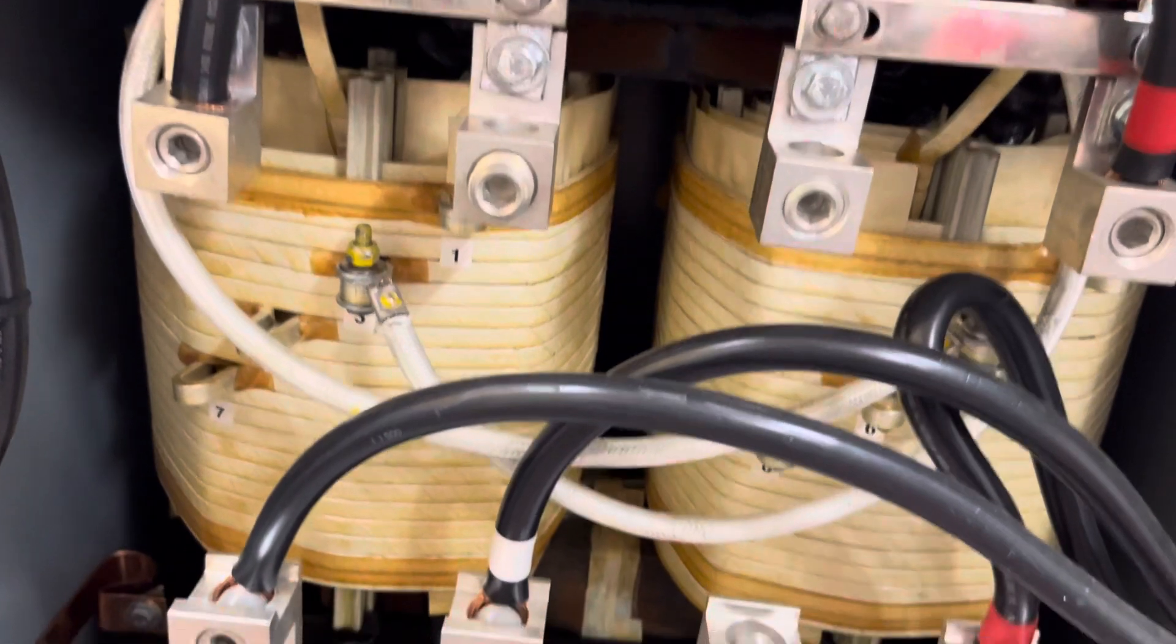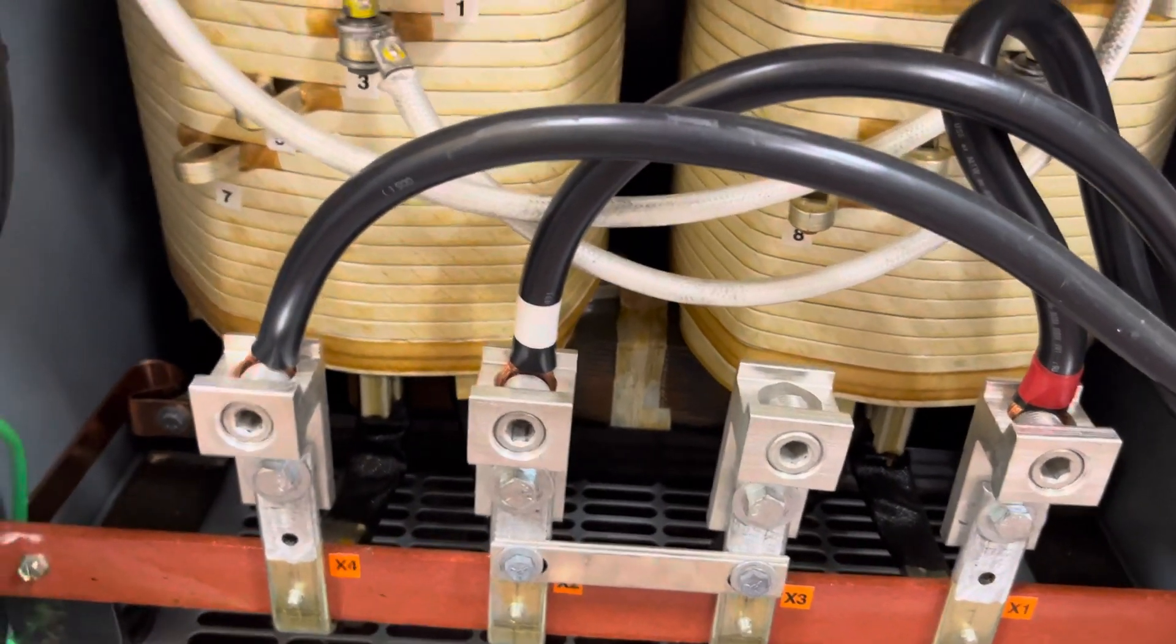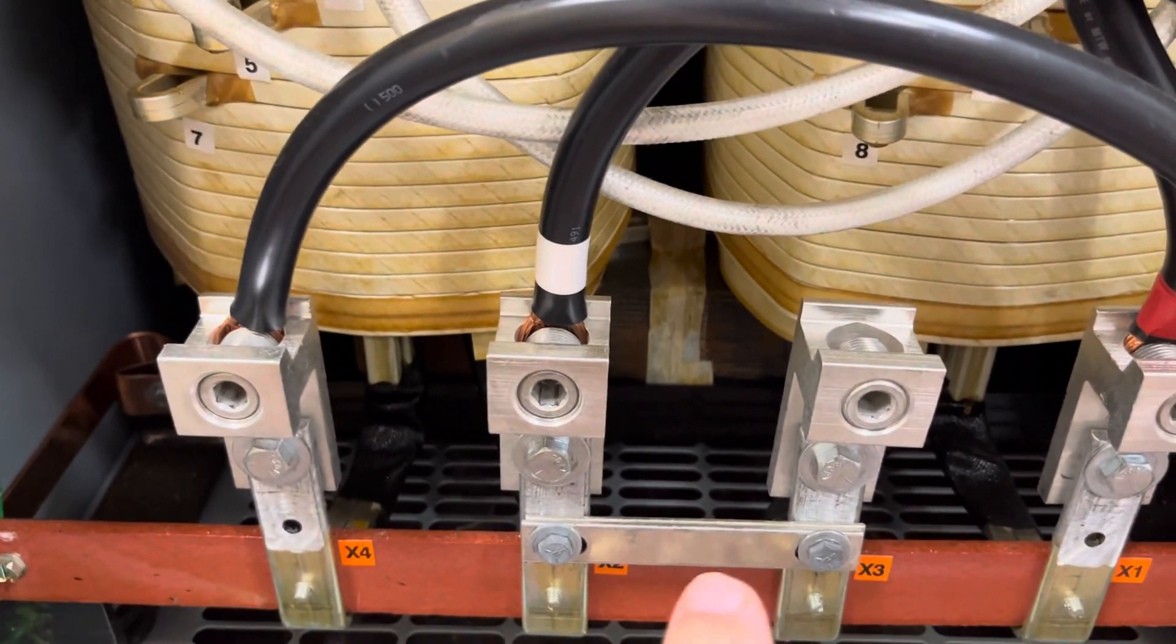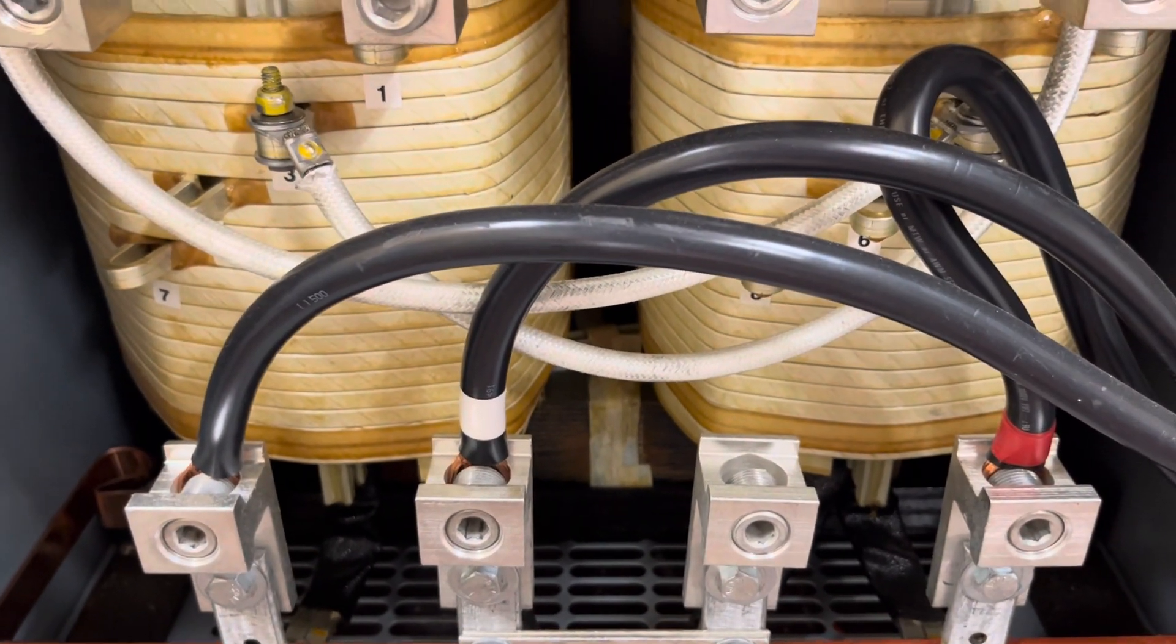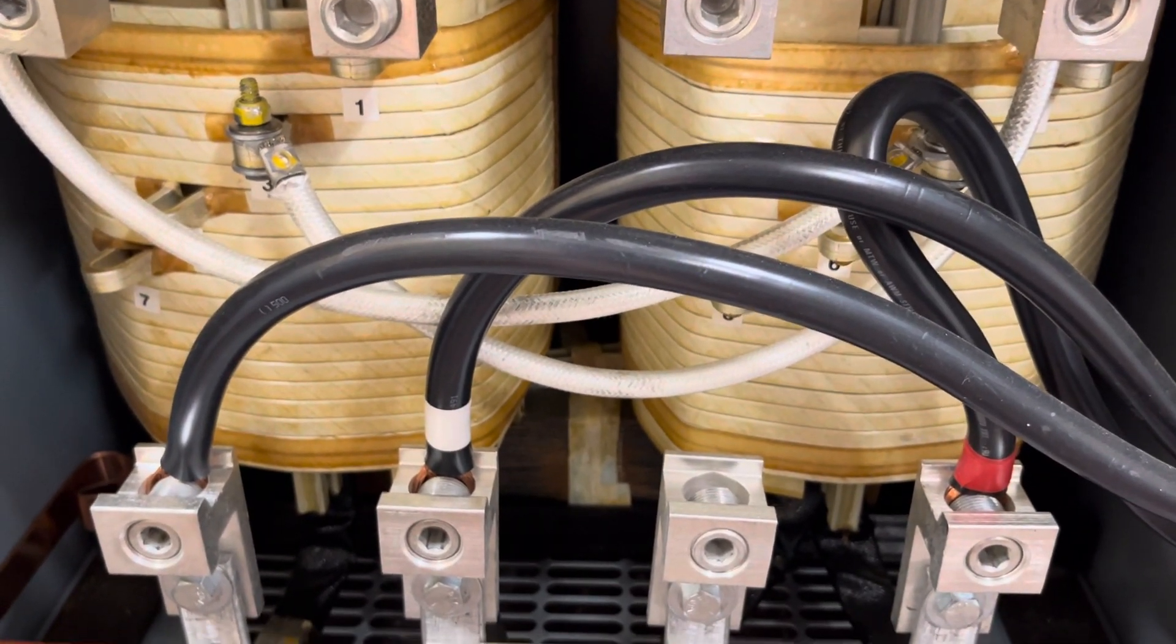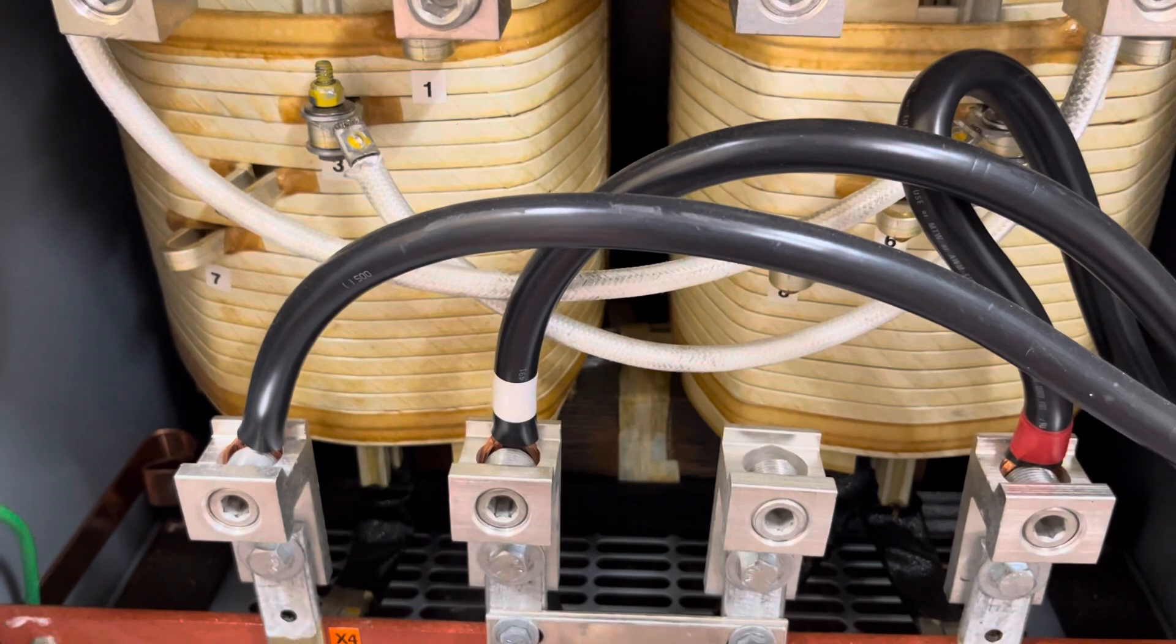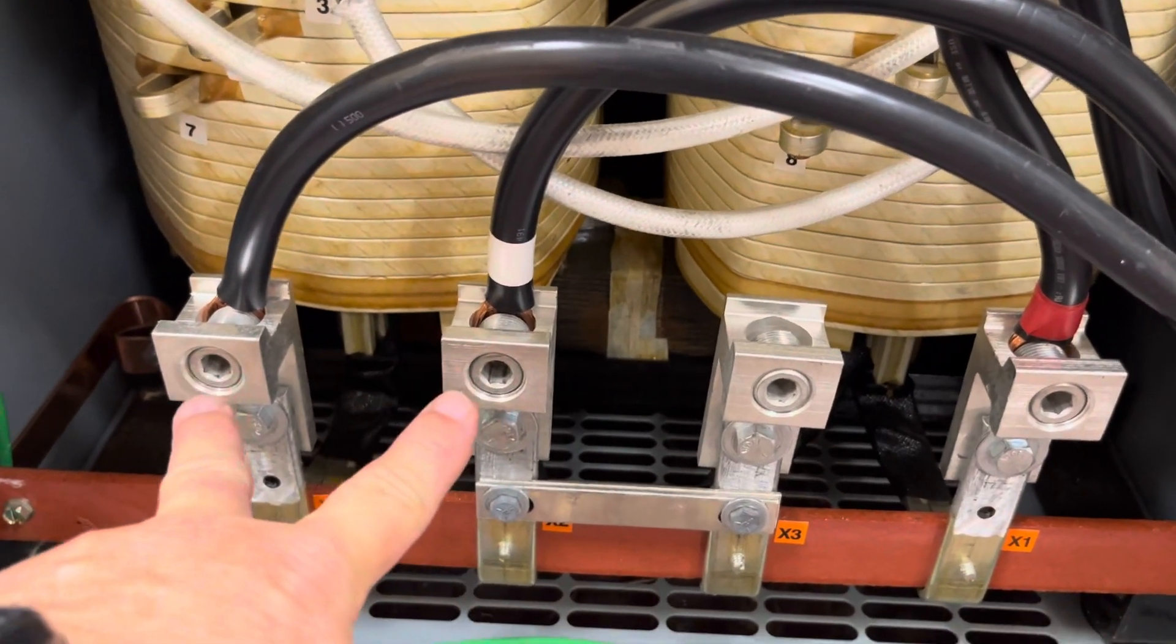Now on the secondary side, it's the same thing, except the windings are 120 volt windings. And in this case, I've kept them in series. So I have X1, which is the other end of the winding is X2, but X2 is in series with X3 and X4. So this winding is in series.